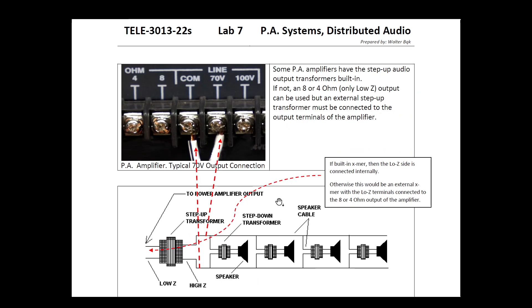Bear with me. There you go — see those wires should be stripped so that once fully inserted inside the screw terminals, the insulation is just pretty much touching the housing of the screw terminal. If the stripped wire is too long, you risk those touching unwantedly, and if the wires touch, they short out and you get unwanted connections. Now, they should also not be stripped too short — once you shove it in, the insulation should not go into the screw terminal, because then you'd be making a connection with the insulation instead of the bare copper.